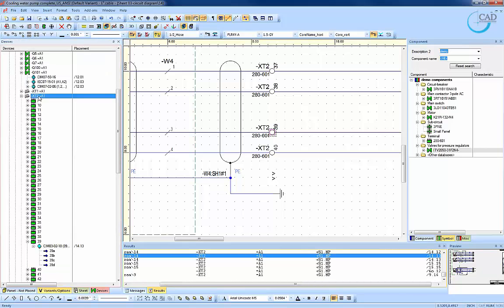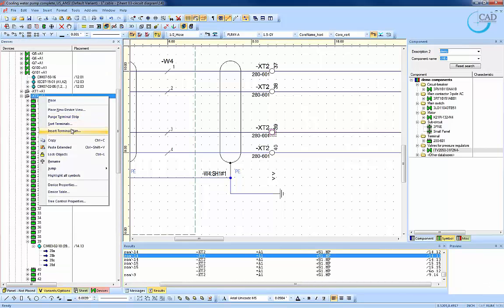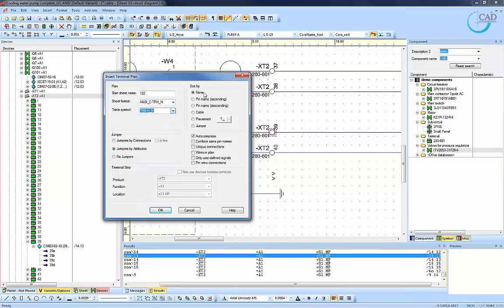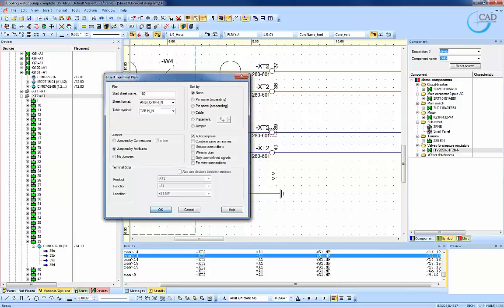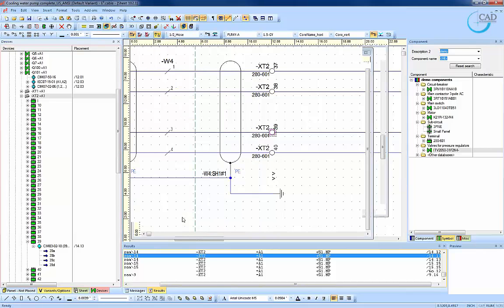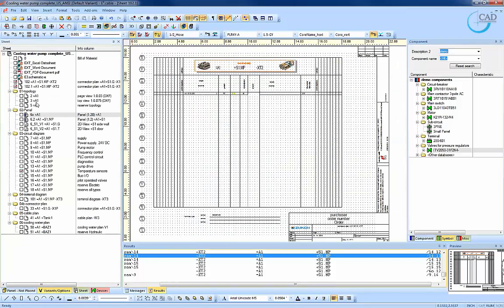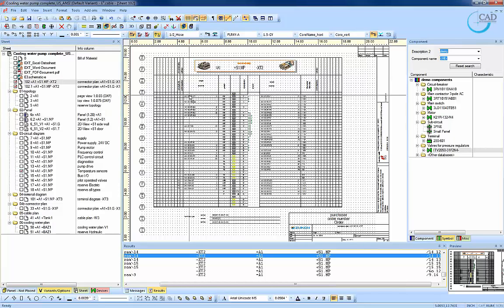From the schematic tool, we can jump to the device table. And from here, we will generate the terminal drawing or plan automatically based on the connections made previously. We can define the sheet format, table symbols, sorting method, and jumper specifications. The generation of the terminal drawings will then be a matter of a single click.